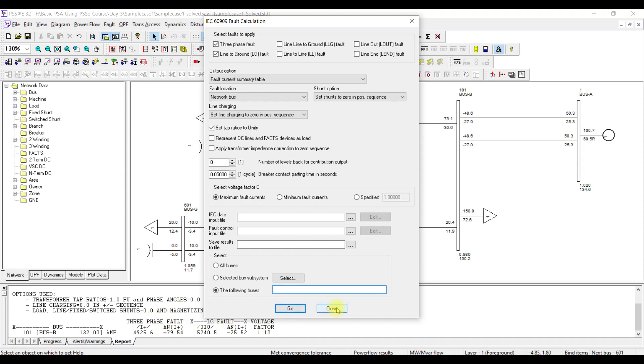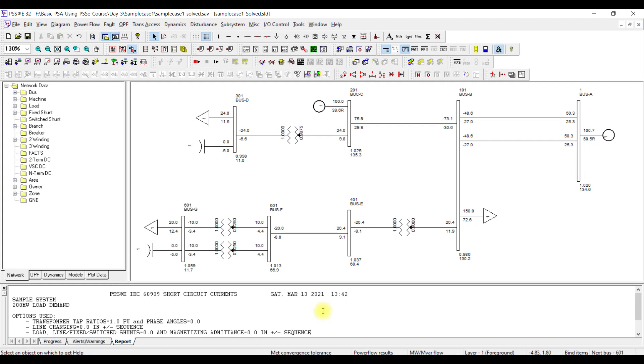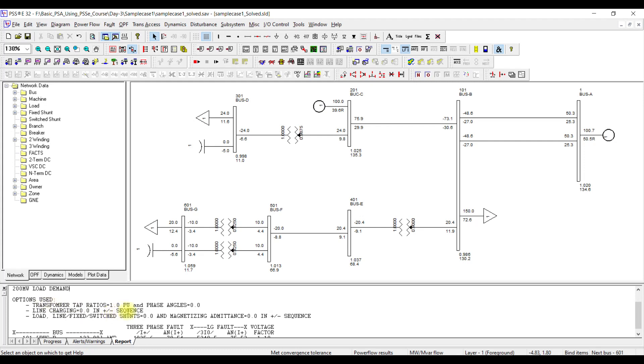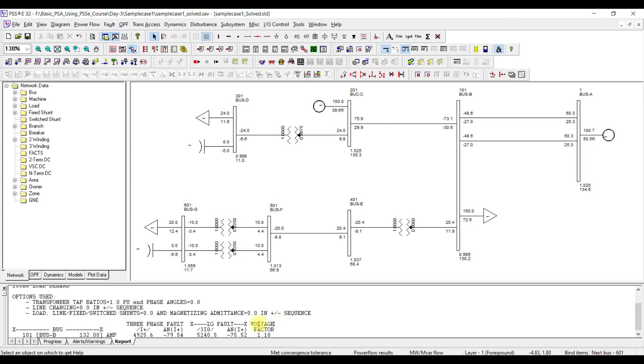When I press OK and go, I get some values. Closing the dialog, the output shows the short circuit was performed using the IEC 60909 method. The case heading and options selected are displayed. The fault current calculated for bus 101 is 4925 amperes for the three-phase fault, and 5240 amperes — or 5.2 kilo-amperes — for the line-to-ground fault. The voltage factor used is the maximum value of 1.1, so these results are based on 1.1 per unit voltage.